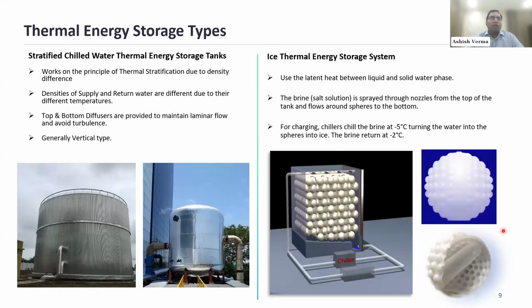Very quickly, I'll cover these energy storage tank types. First and foremost, the most commonly used tank is the stratified chilled water storage tank. These tanks are used in almost all of our district cooling plants, and they serve two purposes. Firstly, they help in shifting the peak from the peak duration, so shaving off the peak load. And the second advantage is redundancy.